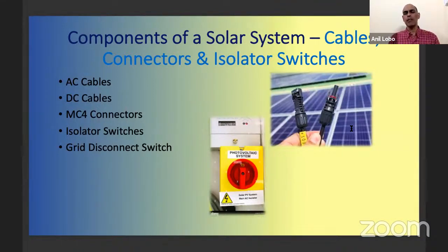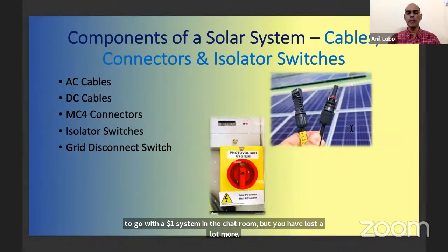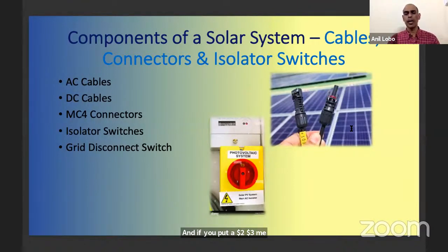If you go cheap on the MC4 connector, instead of spending $2 on a good quality connector, you spend $1. You might have saved a dollar, but you've let yourself down, because a 1% or 2% drop in your voltage and current, over 365 days and the next 25 years, means you have lost more than $1 - probably $100. So it's cheaper in the short term to go with a $1 connector, but you've lost a lot more. If you put a $2 or $3 MC4 connector from a reputable brand, you've saved yourself a lot of money.